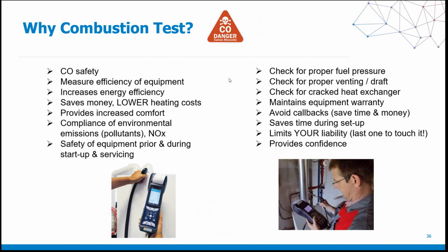Towns and municipalities, or I shouldn't say towns and municipalities, fuel delivery companies, different gas companies, can have different amounts of gas pressure coming to spaces or coming to locations at different times of the day. So it's very, very important that we're actually monitoring gas pressure or evaluating gas pressure as part of our combustion analysis protocol when we're working on a system. We want to check the draft, obviously check the heat exchanger. All these different things are why we combustion test.